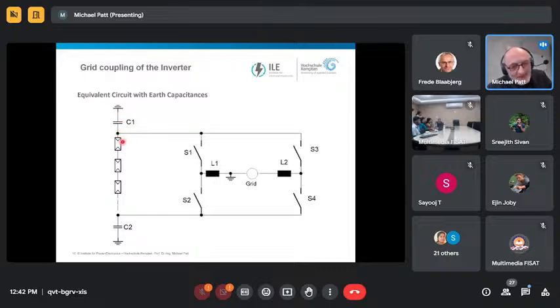The capacitances are between the modules and PE, but you can use a trick to sum them into a capacitor from plus to ground and minus to ground, and these are not neglectable. When you have a 5 kilowatt plant, the size is about 100 nanofarad when it doesn't rain. When it rains, since water has an epsilon R of about 100, you will increase the capacitors here. So they are not neglectable.